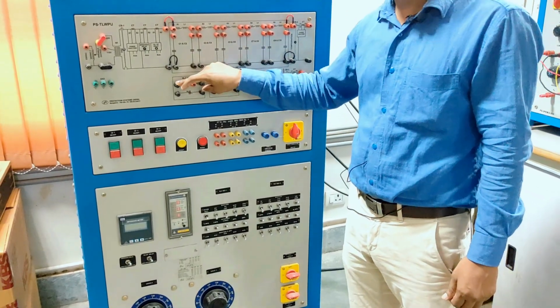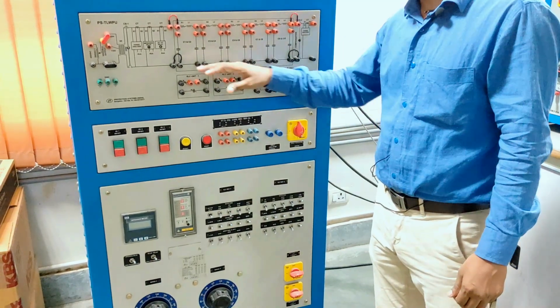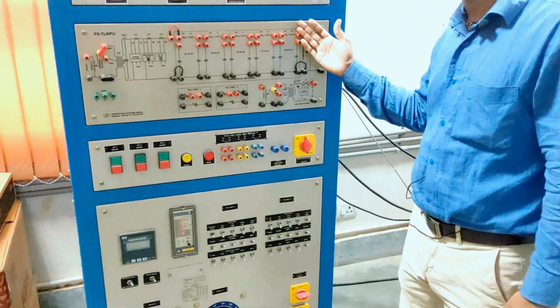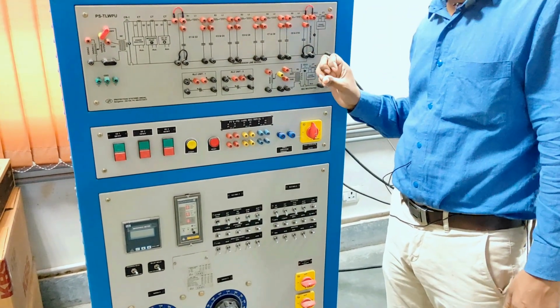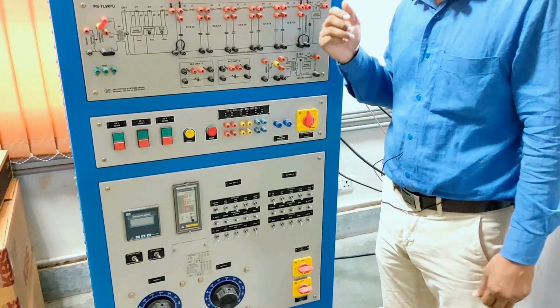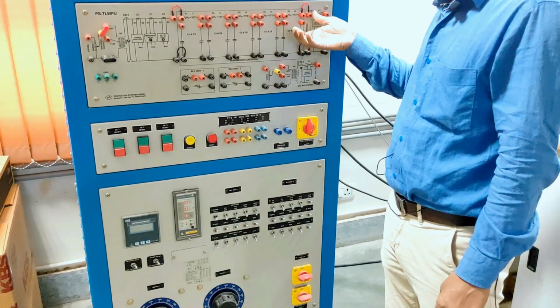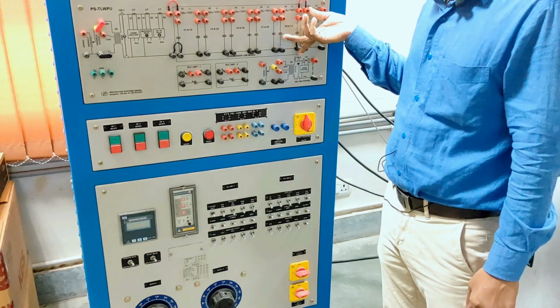Similarly, with RLC compensation with a tap changing transformer, we connect the RLC compensation, then the tap changing transformer, then our compensating terminal. We can adjust the tap changing transformer voltage. By adjusting the different taps, we can have a different voltage, and so produce different reactive power that we can draw from the compensating terminal.